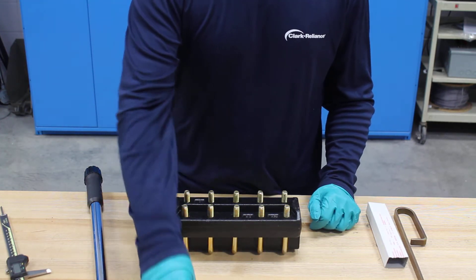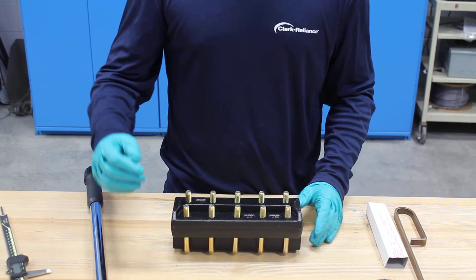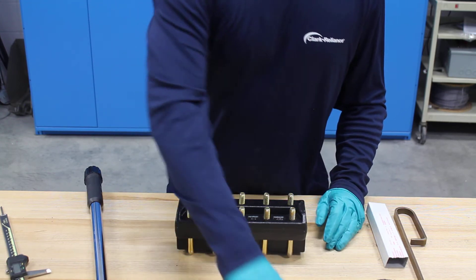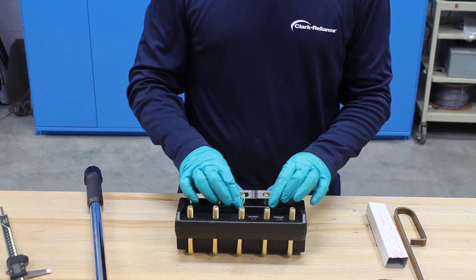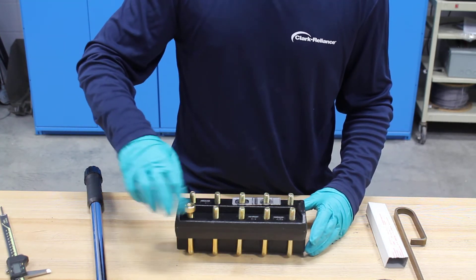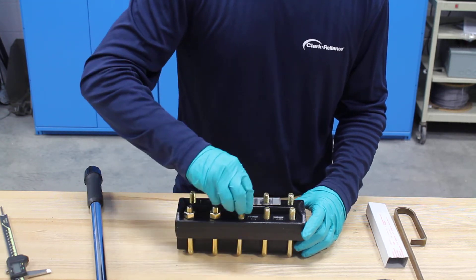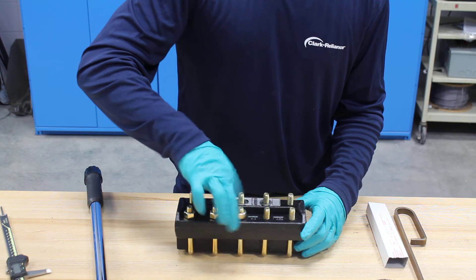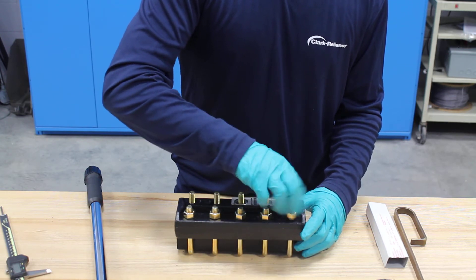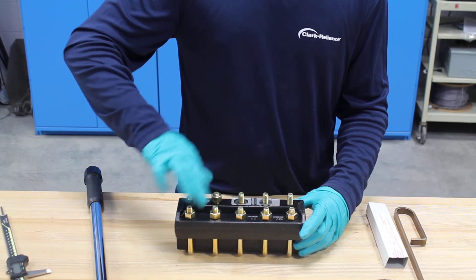Now we're ready to put the nuts back on. You should always make sure that when you're doing this you hit the bolt threads with some Molykote, because you're just trying to get a good torque value on there. If the bolt or nut hangs up it won't give you an accurate torque value. Next thing I'll do is put my rating tag on there — we always do one up on the bottom right-hand side. Put my rating tag on, my two washers, and then I'll start threading the nuts on finger tight.